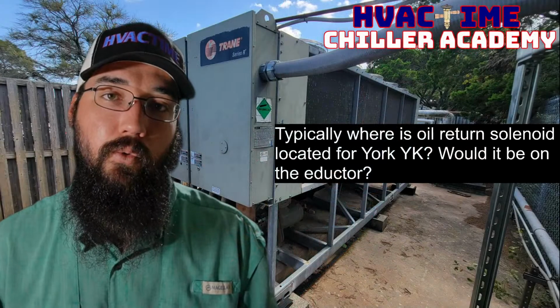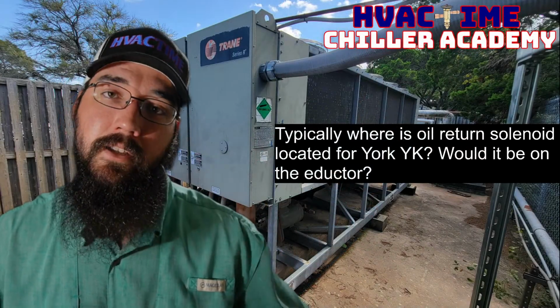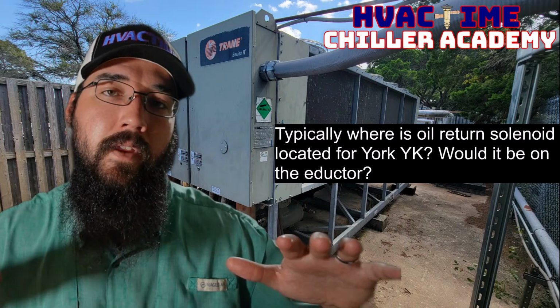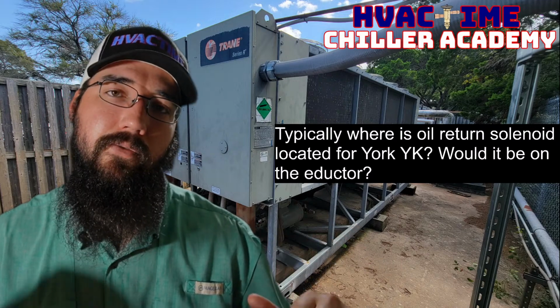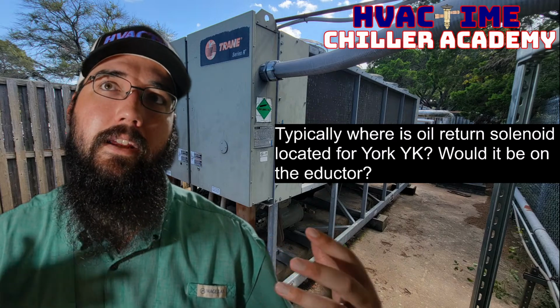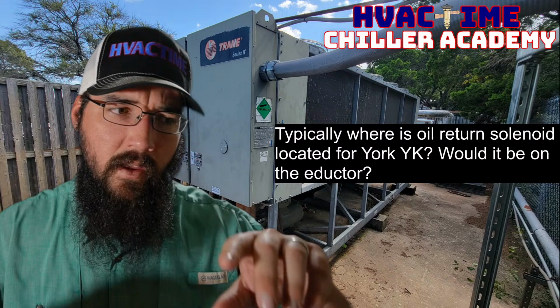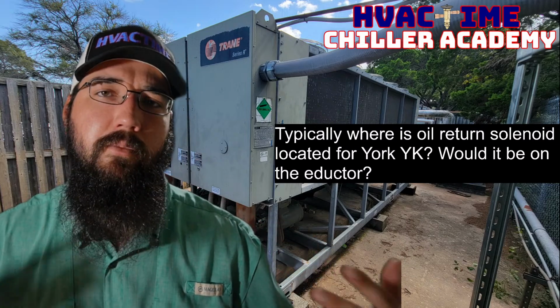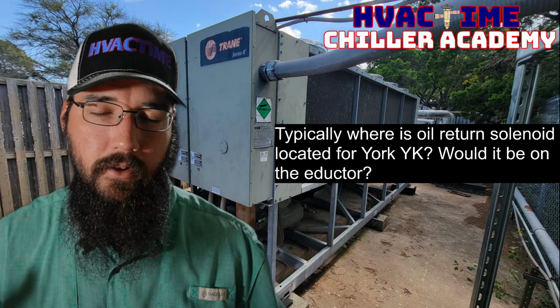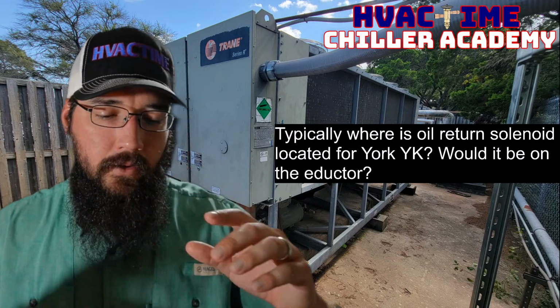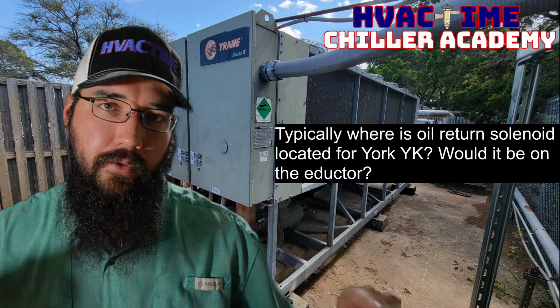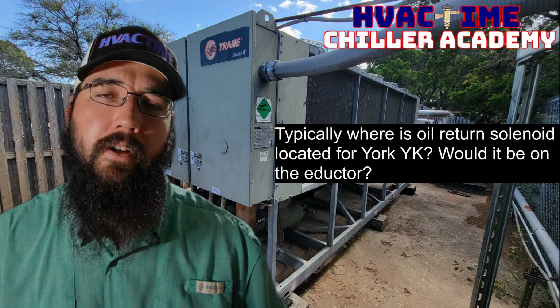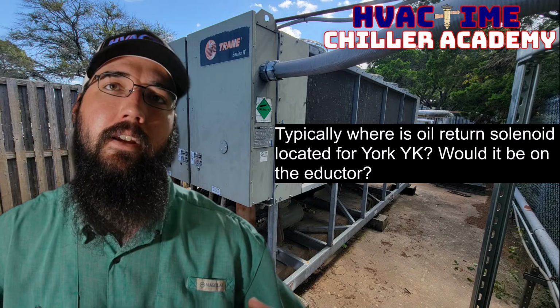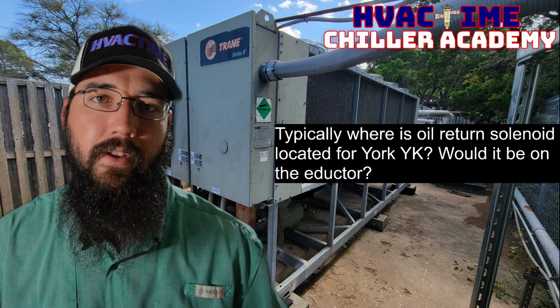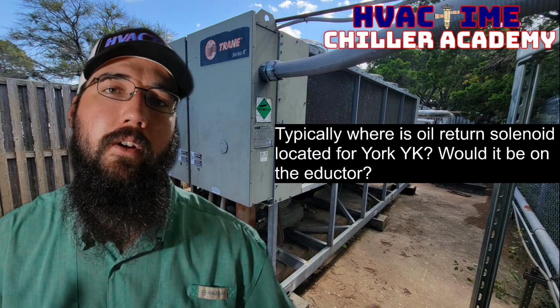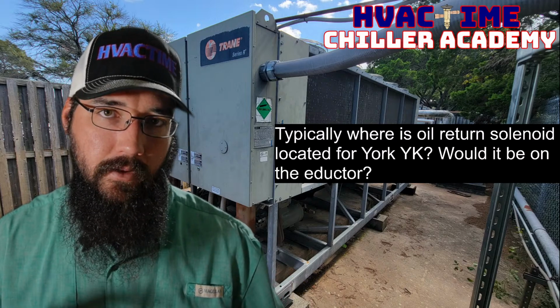Now I want to clarify and put a reminder out there: your liquid level control is really important for controlling the eductor feed. The top few inches, while your machine is running, which is when the eductor works, because it doesn't work at standby - the top few inches of your refrigerant liquid level will be mixed with oil, because as the refrigerant boils, the oil gets caught at the top and mixed in as oil-laden refrigerant right at the top of the liquid level section.